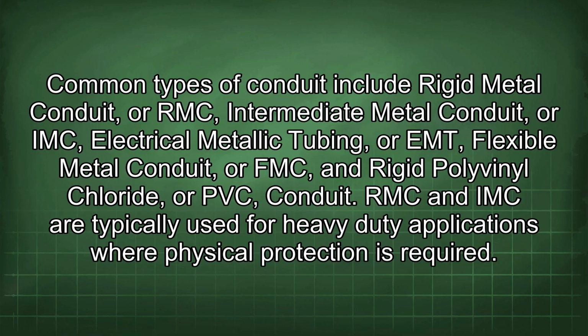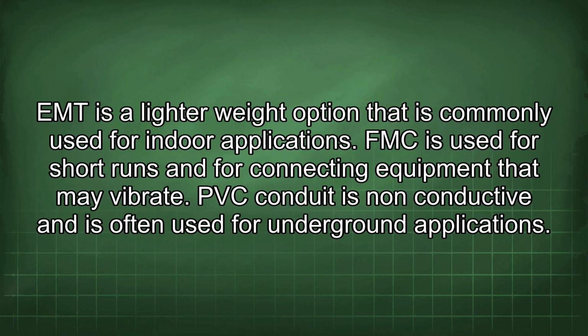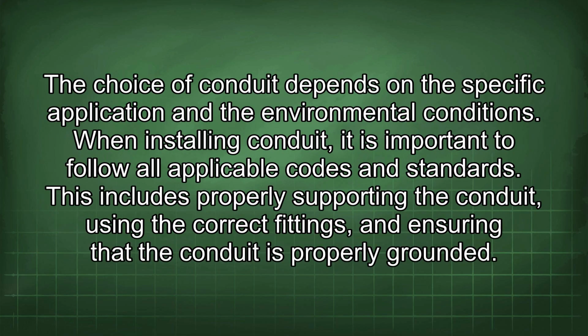RMC and IMC are typically used for heavy-duty applications where physical protection is required. EMT is a lighter weight option that is commonly used for indoor applications. FMC is used for short runs and for connecting equipment that may vibrate. PVC conduit is non-conductive and is often used for underground applications. The choice of conduit depends on the specific application and the environmental conditions. When installing conduit, it is important to follow all applicable codes and standards. This includes properly supporting the conduit, using the correct fittings, and ensuring that the conduit is properly grounded.